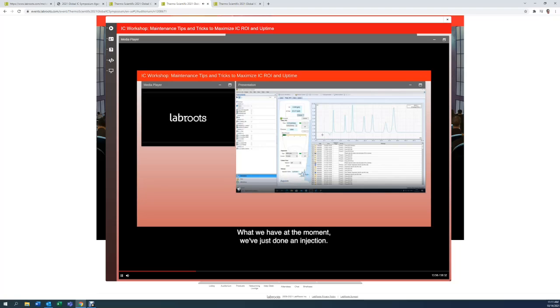What we have at the moment, we've just done an injection. We can just see it finishing here. Let's have a look at the anatomy of this injection, of the chromatogram. The most important thing that I always think on an injection is this bit here. This is the water dip. Everybody ignores the water dip, but it is very important. First off, if you don't get one, chances are you've not actually injected anything. It gives you an idea of the dead volume of the instrument. How it's created is that once you've injected a sample, the sample is effectively deionized by the column. So what we see coming through here is deionized water, which has a conductivity of less than 25 microsiemens. So we see a dip.